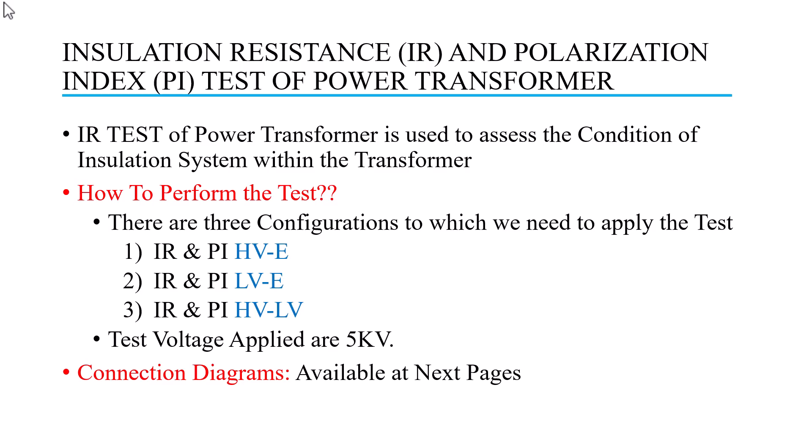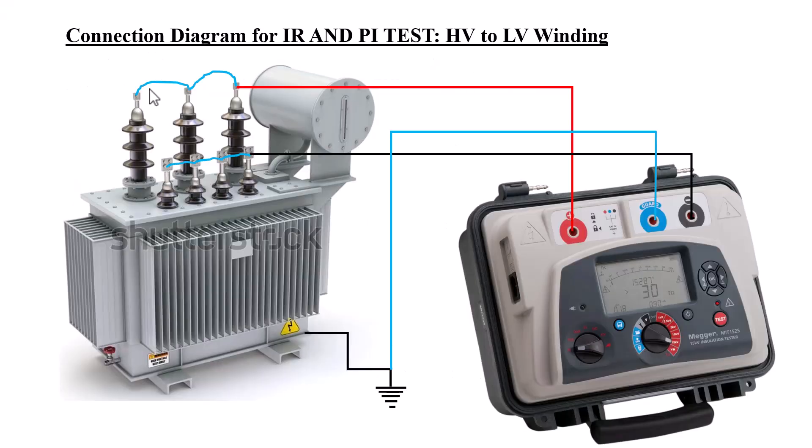In this test, the applied voltage is 5 kV DC. A megger insulation resistance tester is used to perform the test. The connection diagram for all three configurations is shown in the next pages.